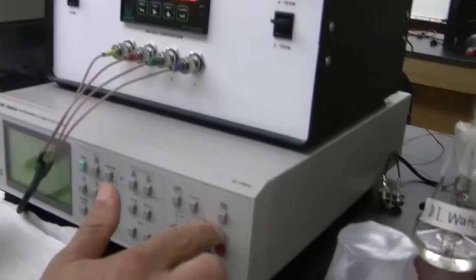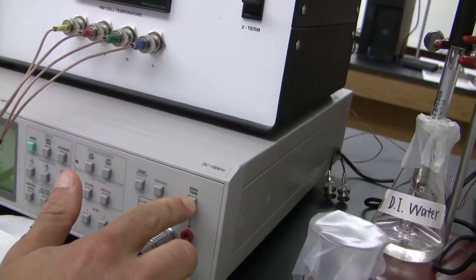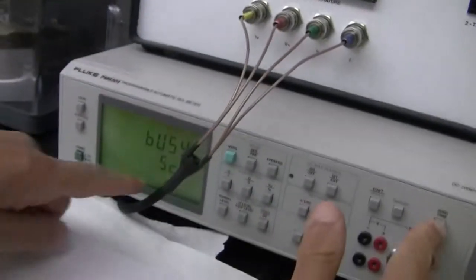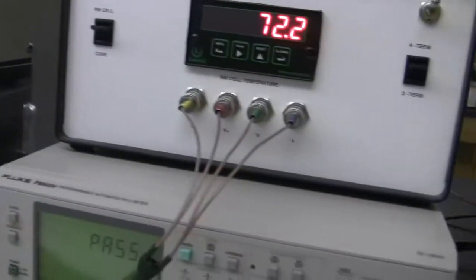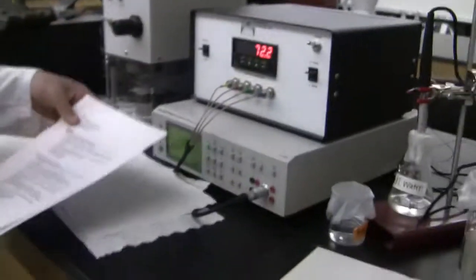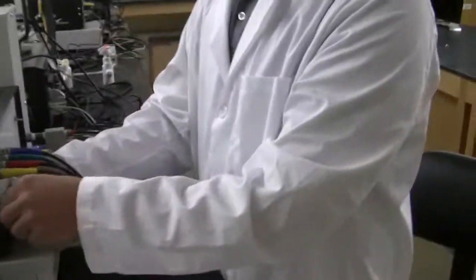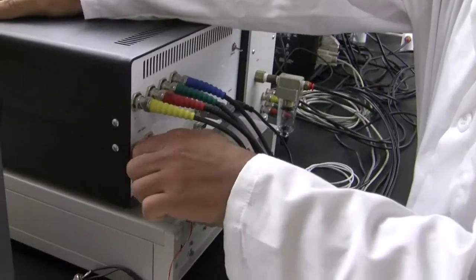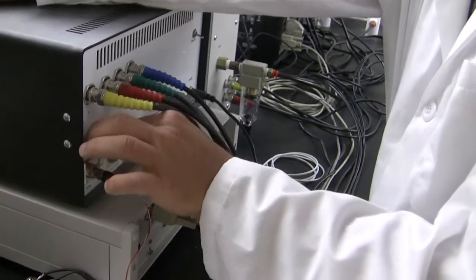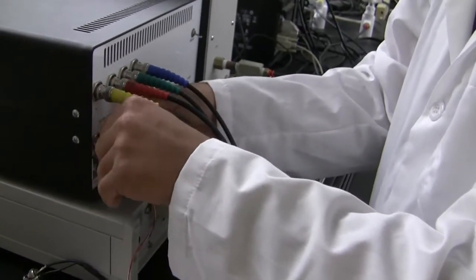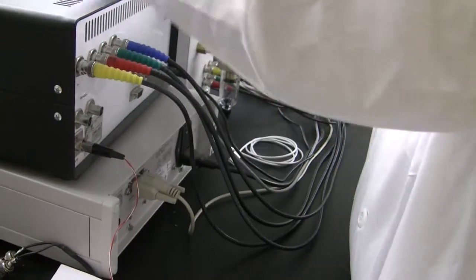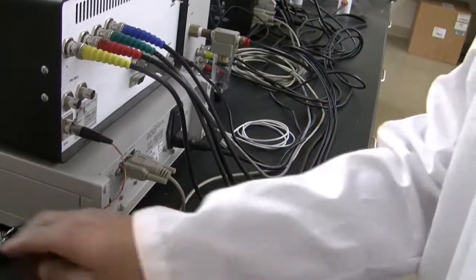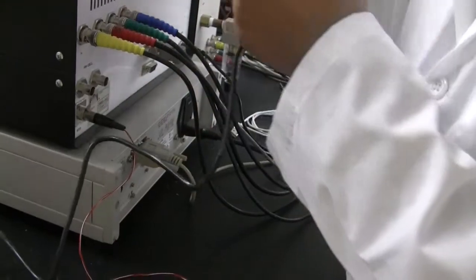And then on the front of your instrument there is a button called zero trim. So you press this button and hold until you see this SCE, and then you leave it, and then it tells you pass. After it tells you pass, you can remove the jumper cable, and now we have finished the first calibration. Come back, you remove your jumper cable, same way. After that, you connect your original BNC connectors that are coming from your cell.